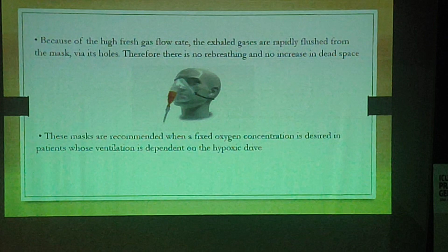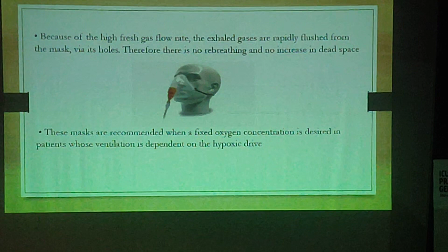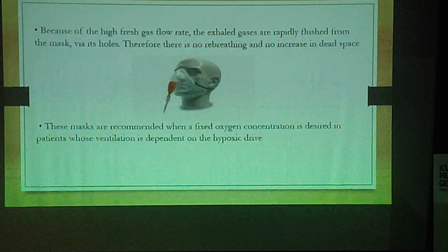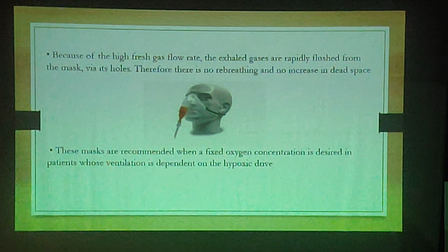These masks are recommended when a fixed oxygen concentration is desired for patients whose ventilation is dependent on their own hypoxic drive. These high flow devices are usually needed in severely hypoxic patients whose oxygen demand is so high that we are not able to meet it with the low flow systems. So these high flow systems deliver oxygen at 20 to 40 liters per minute, and that is how they combat the hypoxic drive of the patient.